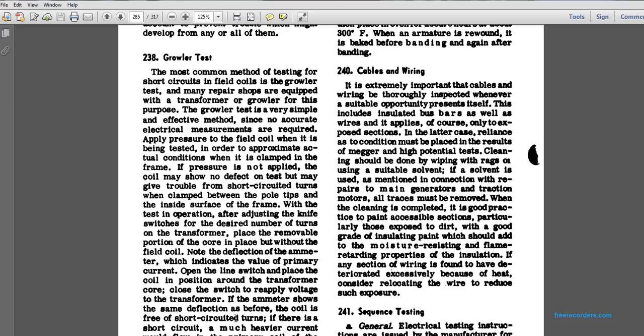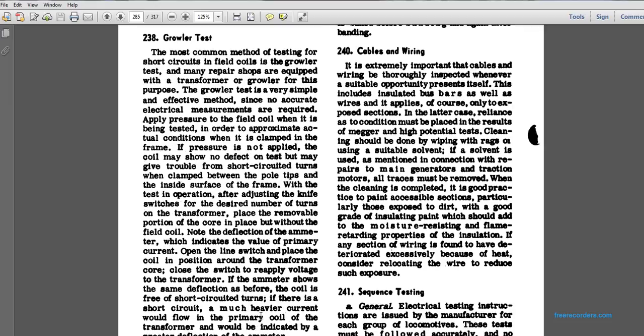Note the deflection of the ammeter. When it indicates the primary current, open the line switch, place the coil in position around the transformer core, and close the switch to reapply the voltage to the transformer. If the ammeter shows the same deflection as before, the coil is free of short-circuited turns. Therefore, it is not short-circuited.